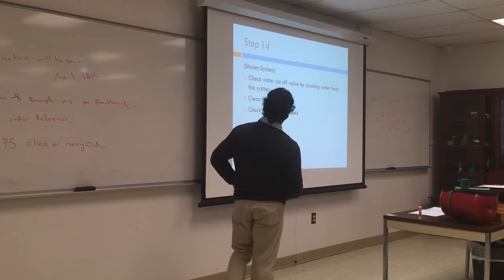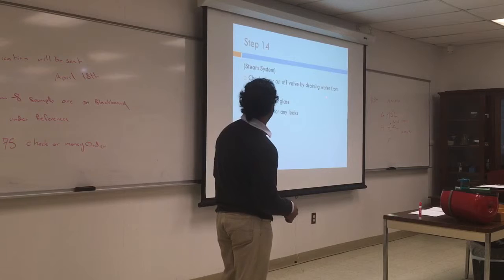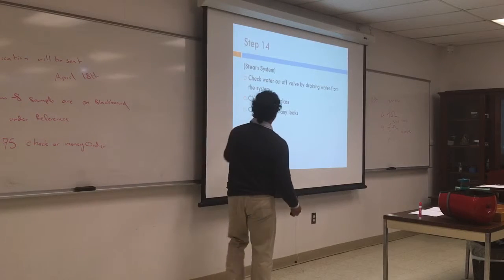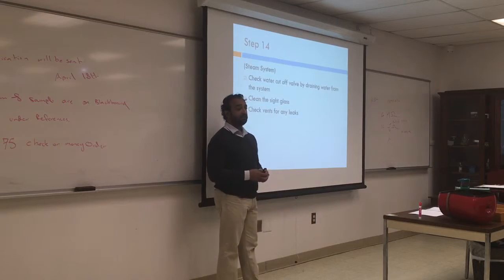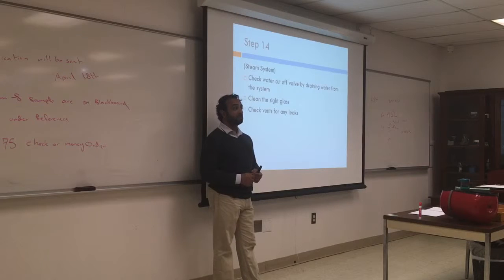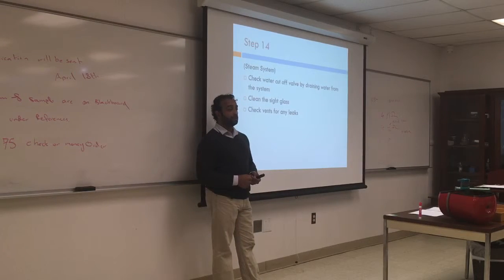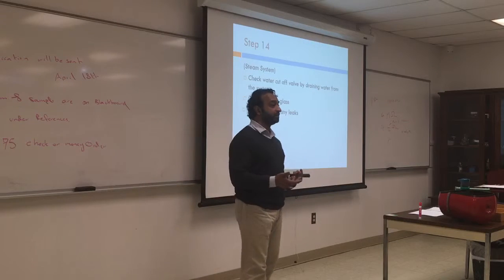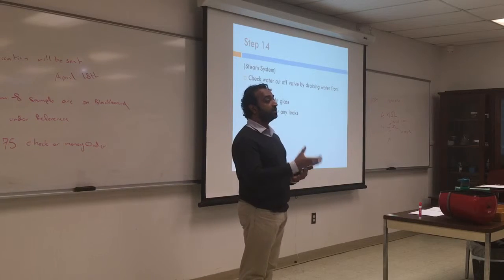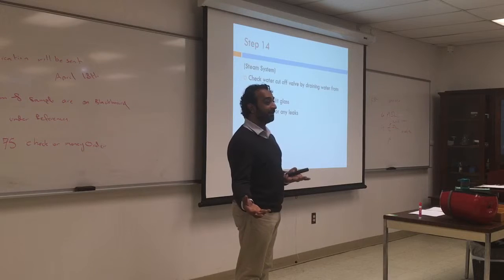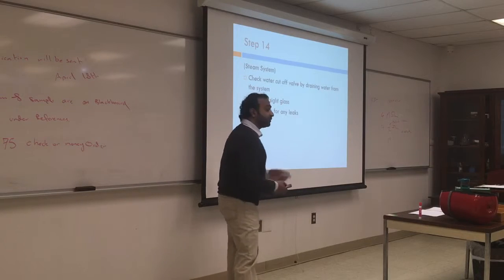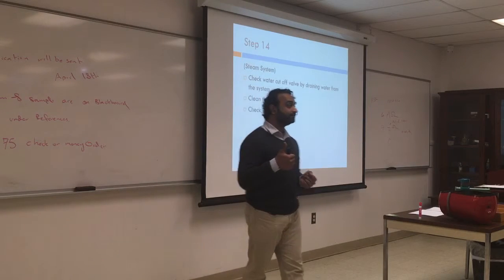For steam system, check the water cutoff valve by draining the water from the system. So we did that in the lab. Keep it running and drain the system and make sure it will cut off. That is very essential. Do it slowly, so you won't drain the boiler, and if the water cutoff is malfunctioning, you don't want to overheat it. So make sure it cuts off when the water is drained. Got that?